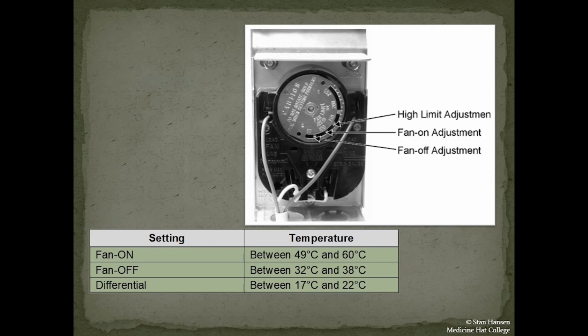In a lot of older units, we see a combination unit that contains both the fan control and the high limit control. If this is the case, we have to make sure that the high limit adjustment is higher than the fan on adjustment. We want to make sure that the high limit will activate if the plenum gets too hot, but we don't want it shutting off the gas too early either.